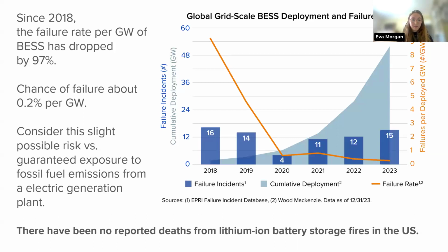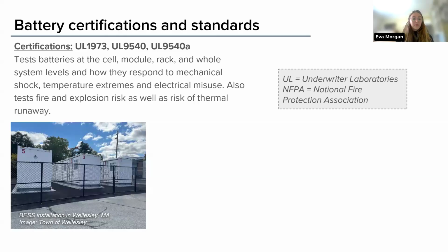There are quite a few certifications that batteries can go through, specifically lithium ion, to test all of the cells, modules, and racks. They're even tested on a whole system level and how they respond to mechanical shock, temperature extremes, and electrical misuse. So if a battery installation is being proposed, it's important to make sure these batteries are going through these specific certifications. They also test fire and explosion risk and the risk of thermal runaway.